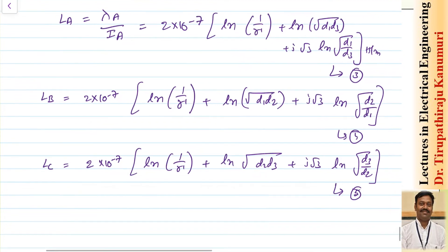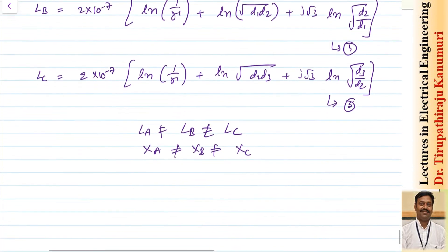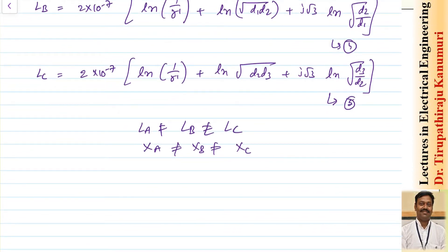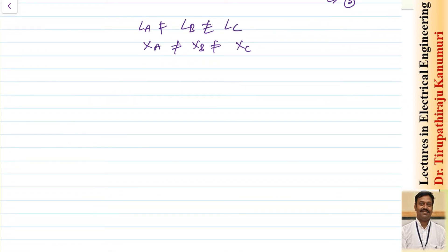From these three equations we can observe that the inductances are not equal because the distances are different. If distances were equal, all terms would be equal. Since they are not, La ≠ Lb ≠ Lc, meaning inductive reactances differ, leading to different voltage drops in each conductor. To avoid this problem, the solution is transposition — each conductor occupies every position so that unbalance is compensated.